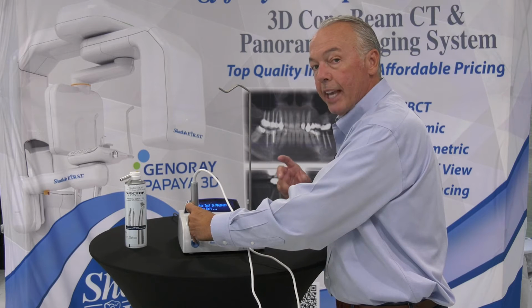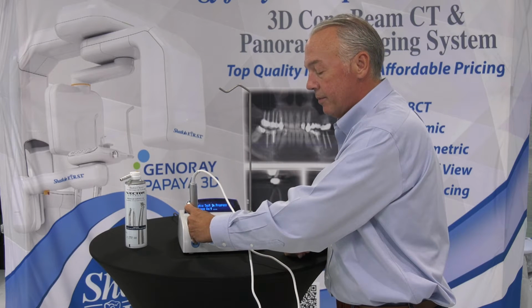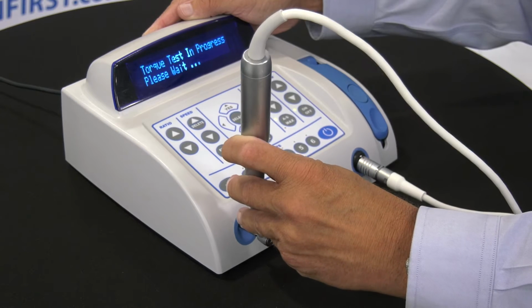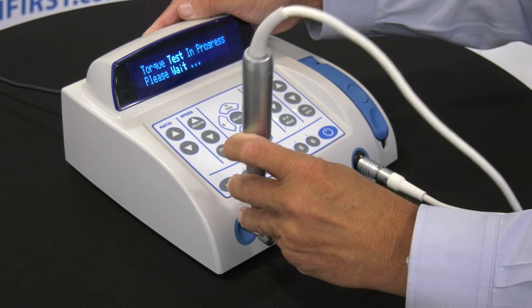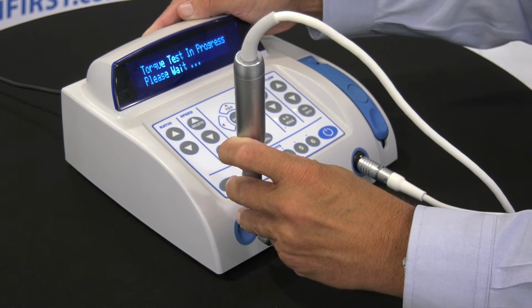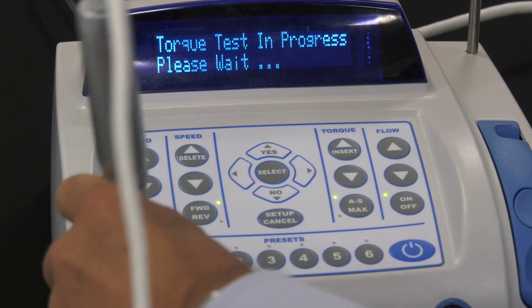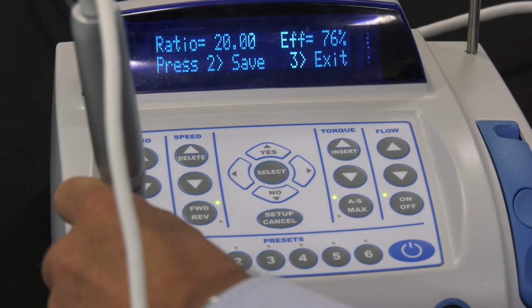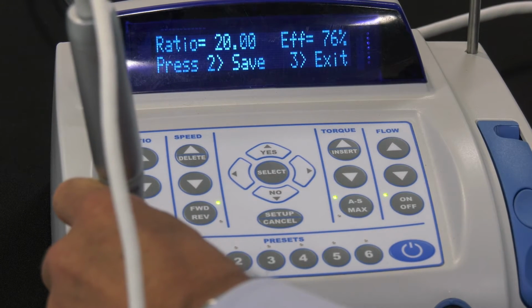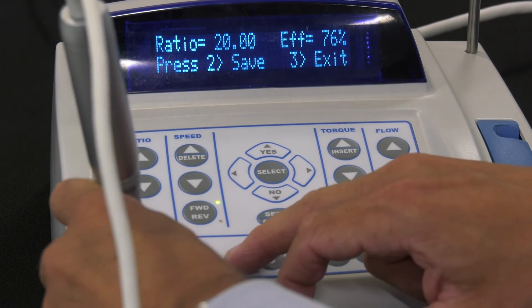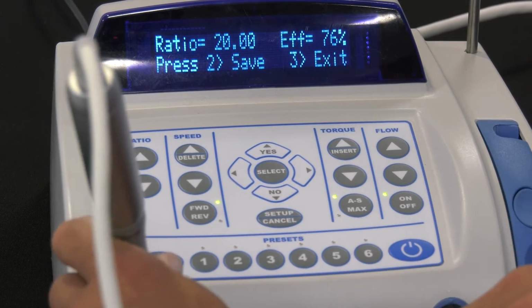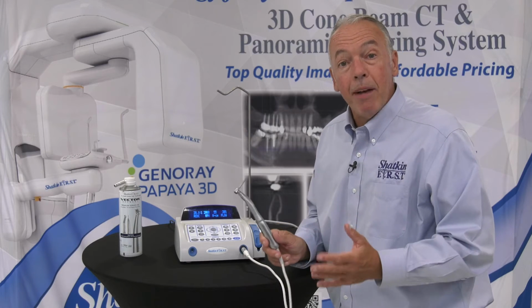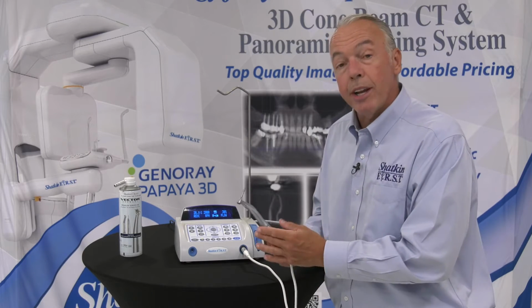You'll hear a few mechanical sounds occurring, and you'll want to hear this sound. And there's my ratio, dead on at 20-to-1, which I want. I'm going to save this. Number 2 is save, number 3 is exit, number 2 is save. So I can now take this out. And keep in mind, it takes less than a minute to calibrate the handpiece.